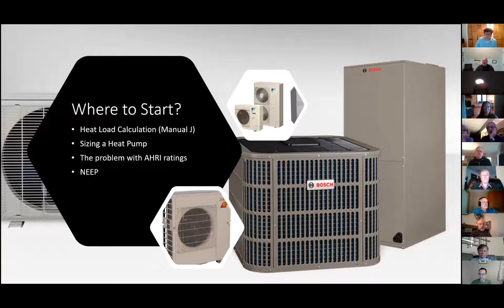There's also a problem if you look at just AHRI ratings—they only rate heat pumps at 47 degrees and 17 degrees. There's a wonderful website, the Northeast Energy Efficiency Partnerships, that puts out statistics and data on heat pumps down to 5 degrees, so you can find out what heat pumps will actually do at that temperature. I can show you that a little later after everybody's done.